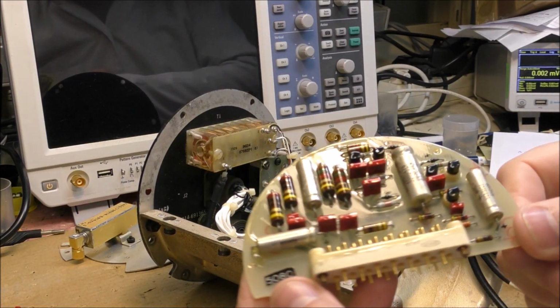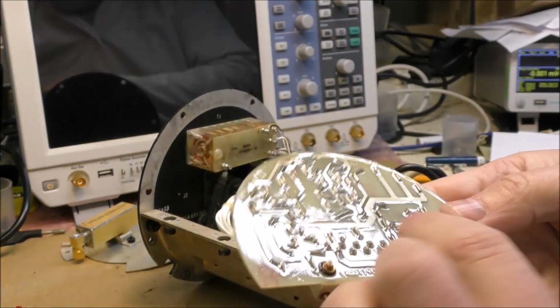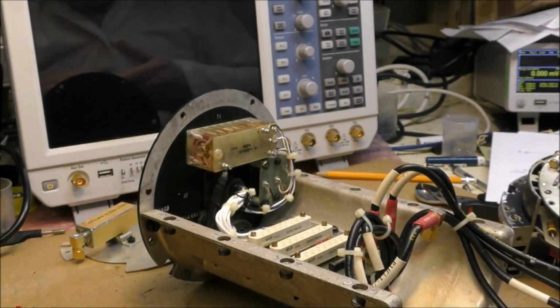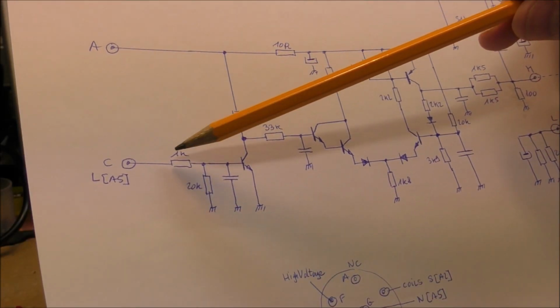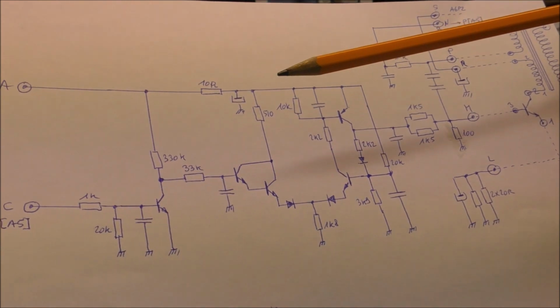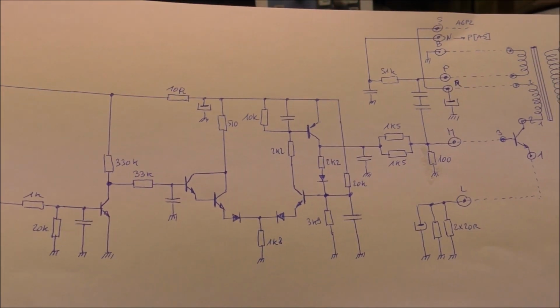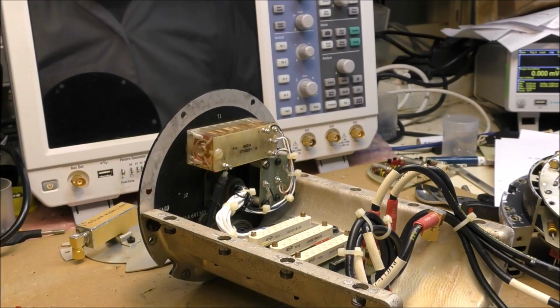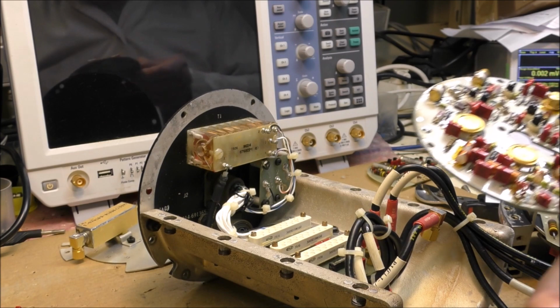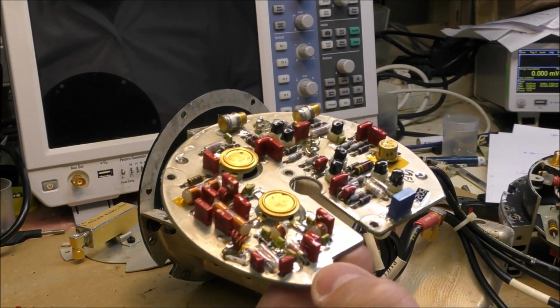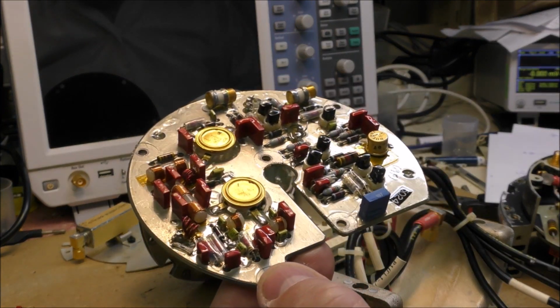This is the circuit of that board. This is the board A3. There is an input here which permits to activate this power supply. The frequency is normally about 52 kHz. After a given time, the high voltage is replaced by a high frequency generator, which is this board here. So I have done the complete reverse engineering of this board also.